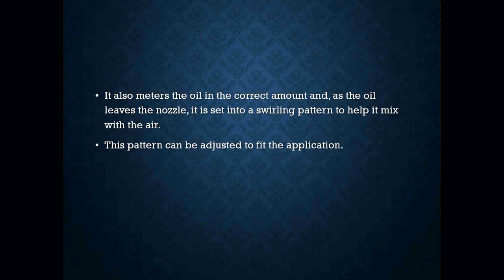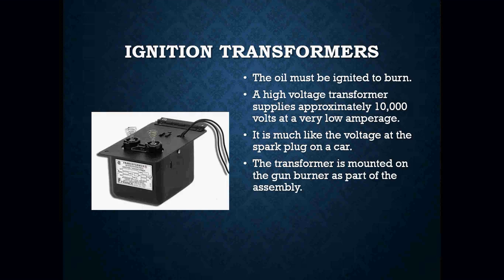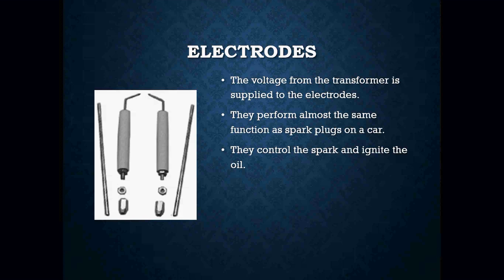The pattern can be adjusted to fit a specific application. Your ignition transformer — oil has to be ignited — is a high-voltage transformer that supplies approximately 10,000 volts at a very low amperage, much like the voltage at the spark plug of a car. The transformer is mounted on the gun burner as part of the assembly. Your electrodes receive the voltage from the transformer and perform almost the same function as a spark plug in a car — they control the spark and ignite the oil.